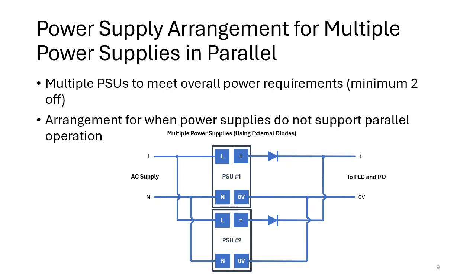And this is what's inside that redundancy module. Effectively, the redundancy module contains those two diodes. And the reason you use a redundancy module rather than just wiring discrete diodes is those diodes might need to be quite big. We're not talking about a simple 1 amp diode here. Often that's 10 amps or 20 amps or 40 amps. So it's quite a beefy diode. So that's why you might use a redundancy module rather than try and just configure this with two simple diodes using a simple terminal. There's another aspect here, which is inside that redundancy module. If you use diodes, there's a volt drop across the diode.